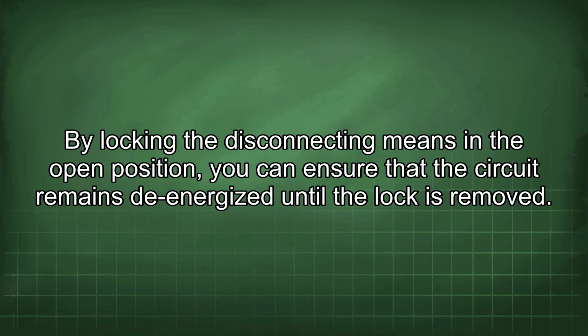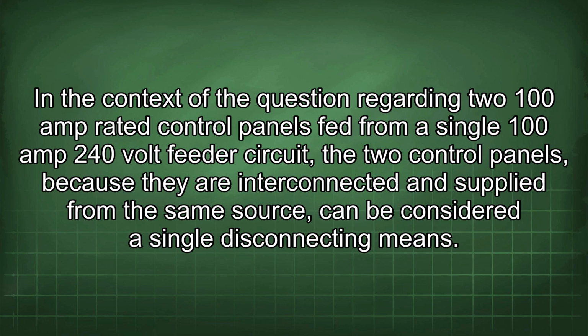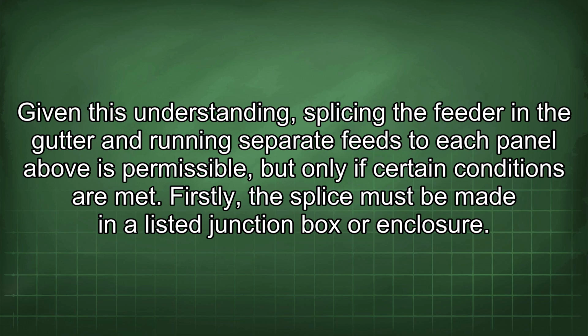is removed. In the context of the question regarding two 100 amp rated control panels fed from a single 100 amp 240 volt feeder circuit, the two control panels, because they are interconnected and supplied from the same source, can be considered a single disconnecting means. Given this understanding, splicing the feeder in the gutter and running separate feeds to each panel above is permissible, but only if certain conditions are met.